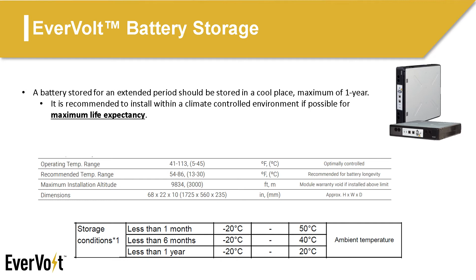Similar to your cell phone battery, the lithium-ion batteries in Evervolt will degrade over time. How fast they degrade depends on many factors, including the charge and discharge rate, the depth of discharge, and the temperature. The sample chart on the right shows the state of charge and degradation over the operational 10 years. You can see that as temperature increases, the batteries will degrade faster. Therefore, it is recommended to install Evervolt within a climate-controlled environment for maximum battery longevity.